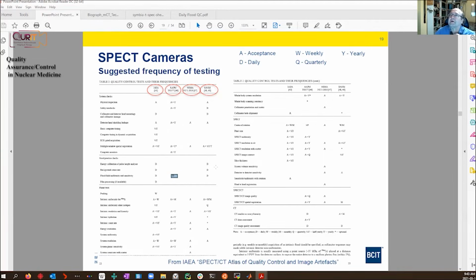So, a question. Let me go to the chat. Are there many developments and technologies in nuclear medicine like SPECT? How much is the QC different? There are slowly evolving changes in the technology for SPECT. There's been a scattering of new technologies, like using solid-state CZT detectors rather than sodium iodide crystals and PMTs. That does have some effect on the specific QC, mainly that the results will be different, and they may have slightly different recommendations on how they're done. In PET, the technology is changing fairly rapidly, and some of the QC will be different.